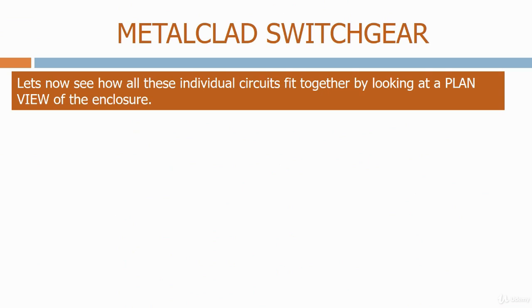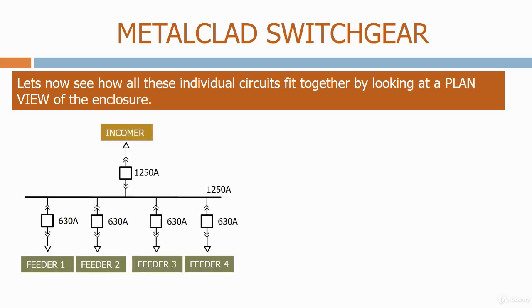Let's now see how all these individual circuits fit together by looking at a plan view of the enclosure. Here's a typical single line diagram for an 11 kV distribution circuit. At the top we have a 1250 amp incomer feeding a 1250 amp bus bar. We then have four 630 amp rated feeders coming off the bus bar. Let's see how these circuits are connected in practice.